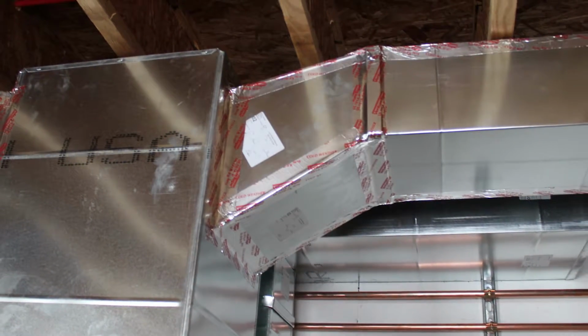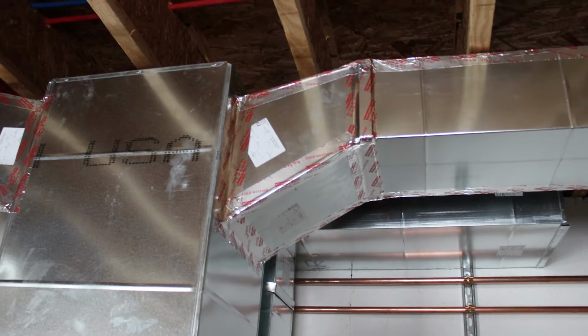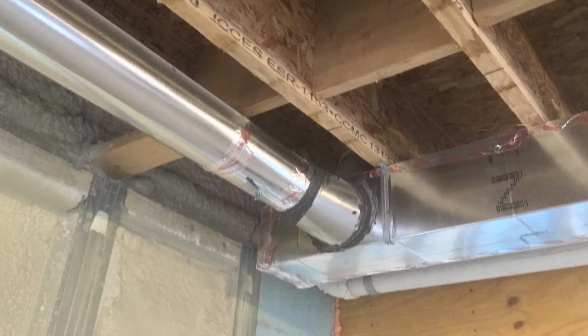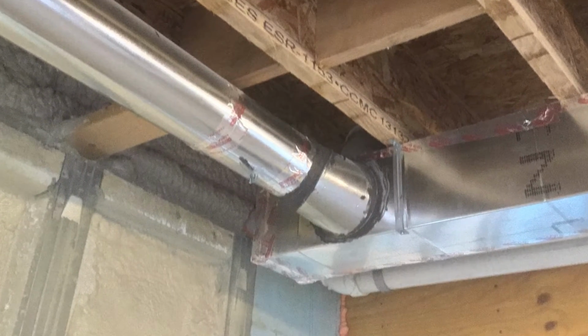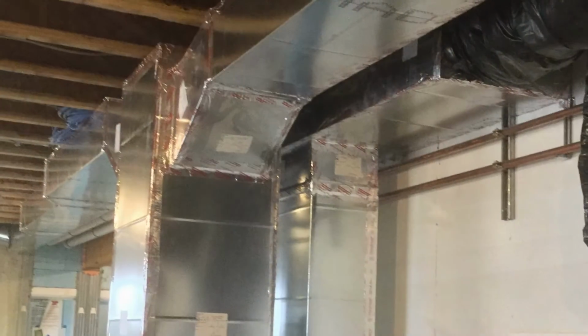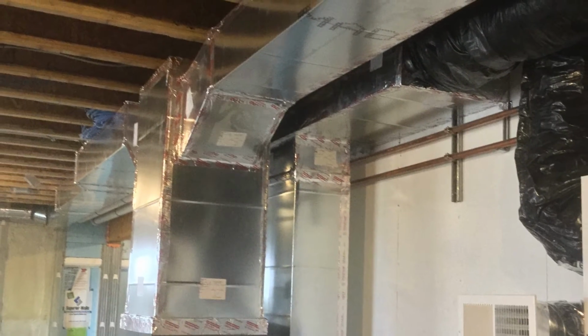Ductwork in the attic provides an opportunity to lose conditioned air through leaky ductwork and inadequately insulated ductwork. This is an item that should not be overlooked in design, and whenever possible, chaseways and bulkheads for ductwork should be designed within the thermal envelope to eliminate the need to route ductwork within the attic space.